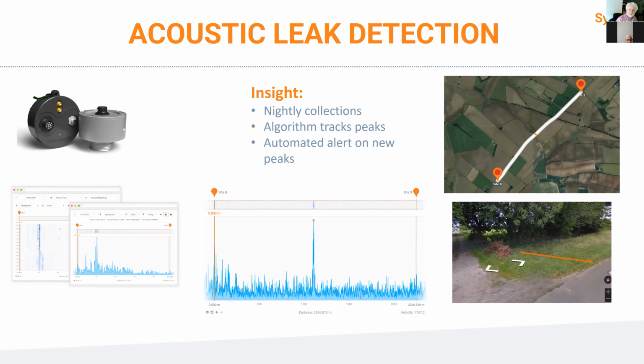And then day after day, night after night, if we get consistent results being picked up, what you see on the left-hand side is a blue sort of strange vertical line with red X's through it. So this is the algorithm tracking those peaks, and we raise an alert when there's a voting system. So if we get 7 positive noise sources in the same position over 10 correlations, then the alert would be raised automatically and emailed to the client. So what we try to avoid is nuisance alerts caused by some noise that happens at any one particular moment that might not actually be anything other than a truck idling or something going on in the network at that moment. Next slide, please.